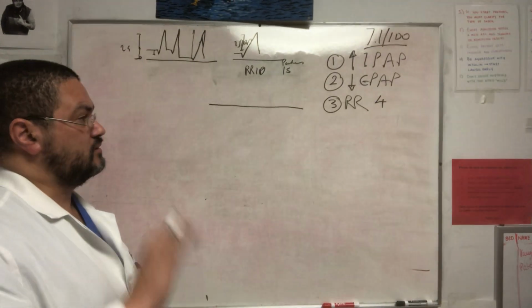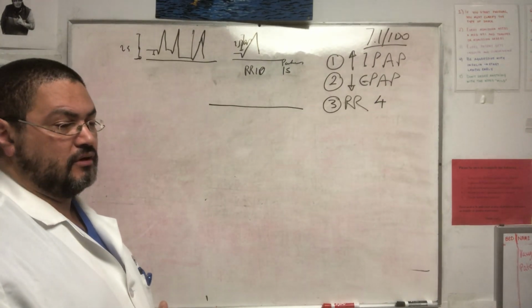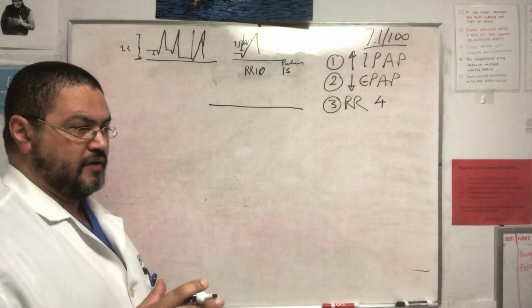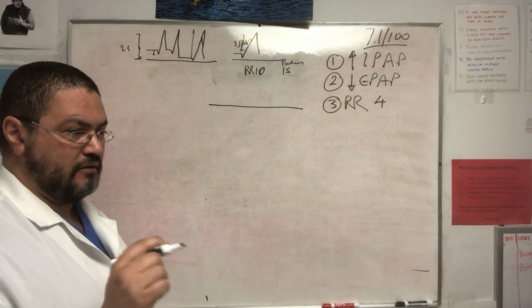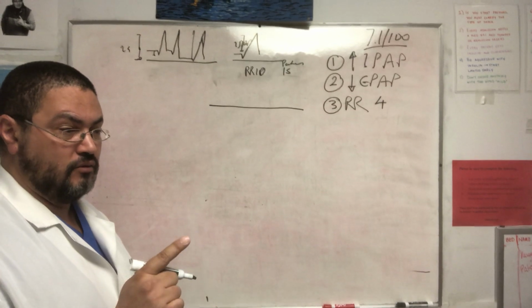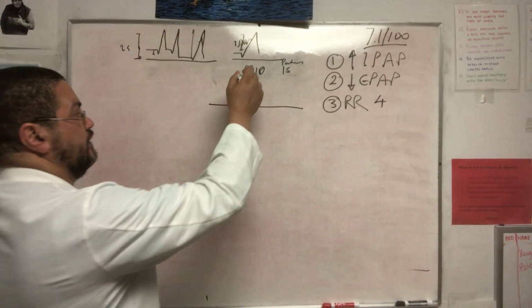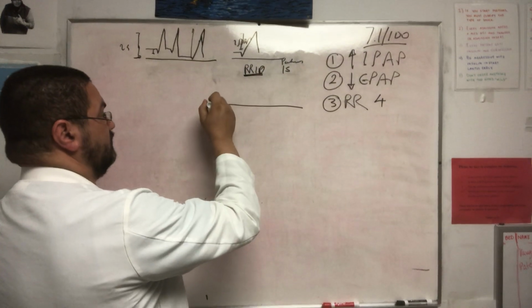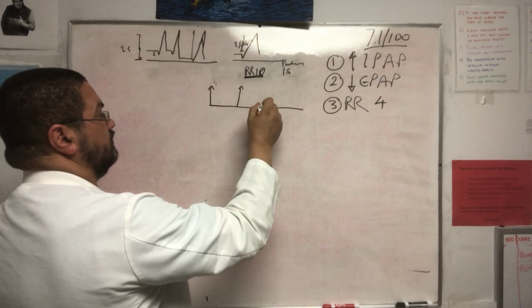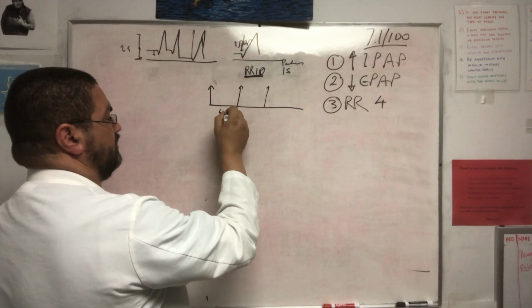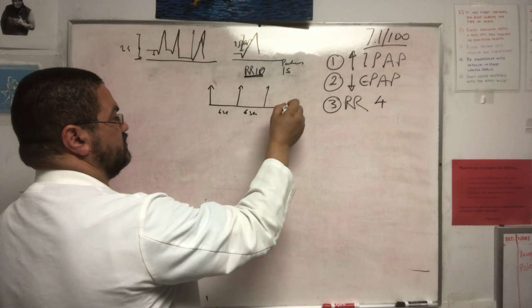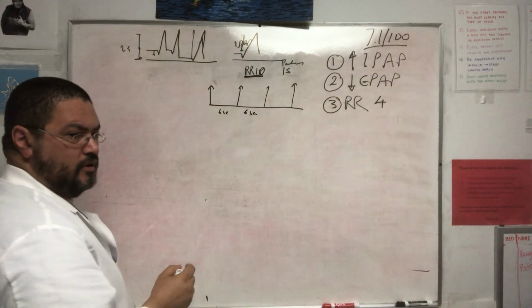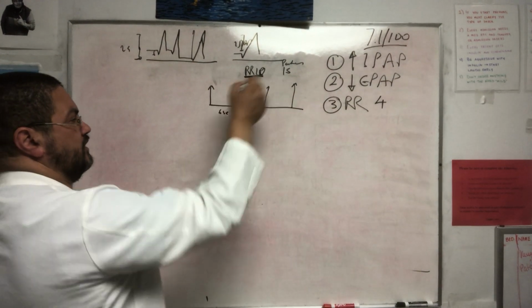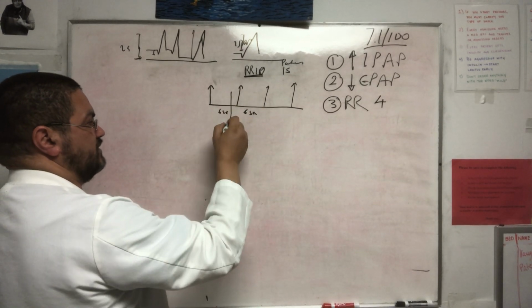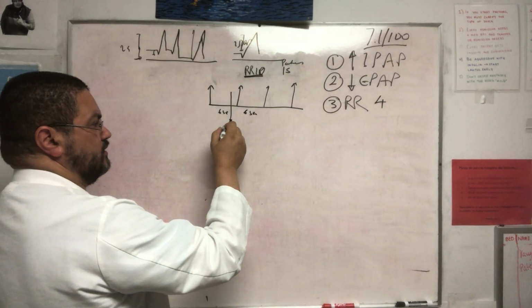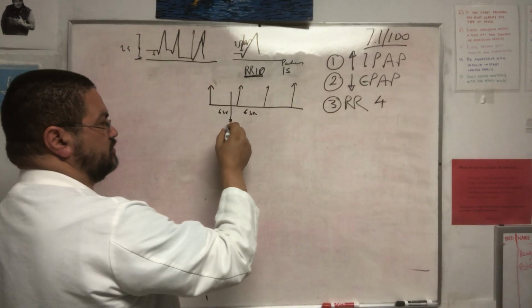Right, that's another lecture. But in general, new vents and new BiPAPs will have a refractory period that will detect when you got the last breath. So if your respiratory rate is 10, that means you have 6 seconds per breath. Every 6 seconds you're getting a breath, no matter if you want it or not. But if you're breathing at 15, in 4 seconds you're going to take a breath. That's a spontaneous breath.